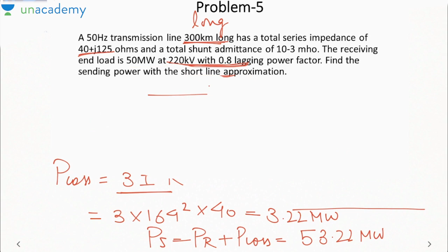But remember, this expression, loss equal to 3I squared R, can only be applied in case of a short transmission line, because suppose it is a medium transmission line and I am using a pi model. The pi model is something like this. The current going here is IR, here is IS. But here there will be some other current I going into the resistance R, which is neither equal to IS nor equal to IR. But in case of a short transmission line, the current passing through the resistance is equal to IS as well as equal to IR. That is why we can directly apply 3IR squared R as the losses in the transmission line. But for any other transmission line, the current passing through the resistance is neither equal to IR nor equal to IS. So it is better that you do not apply this method.